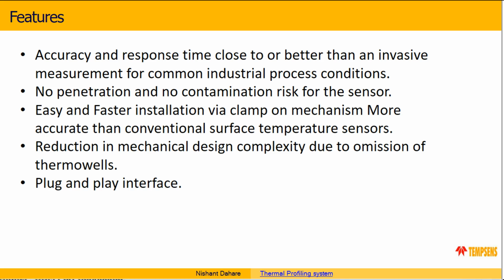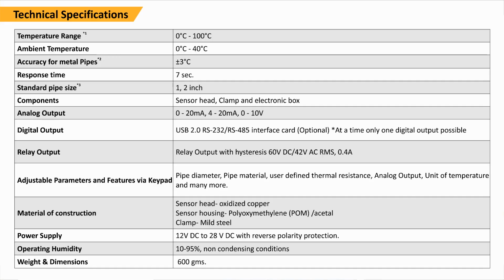So the basic idea about this sensor is that the temperature range goes from 0 to 100 degrees Celsius, and the ambient temperature goes from 0 to 40 degrees Celsius. As of now, we have also developed a sensor for 0 to 300 degrees Celsius, but right now we are providing the 0 to 100 degrees Celsius solution only. When the fluid temperature varies from 0 to 100 degrees Celsius and the ambient temperature is 0 to 40 degrees Celsius, we can give you plus or minus 3 degrees Celsius accuracy, even plus or minus 2 degrees Celsius. And when you do a 2-point or 1-point calibration, you can get accuracy of less than 1 degree Celsius. The response time is basically 7 seconds.